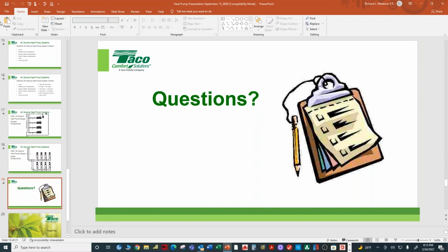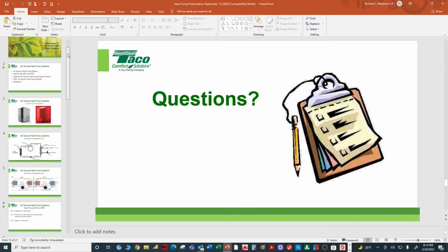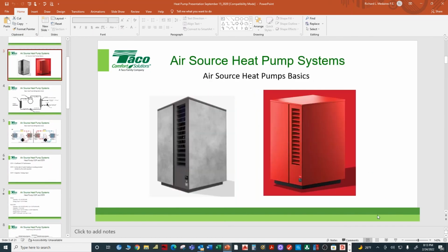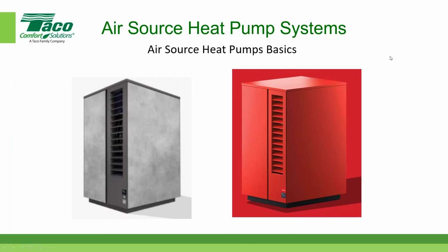I would like to address the question about the ones that are used as terminal units. Someone made the comment: we just changed the high rise from 545 heat pumps to chilled water fan coils. They're notorious for tripping out. I believe the terminal unit heat pump manufacturers have done a heck of a job making their products a lot better than that. That issue's not as prevalent these days, the noise and tripping out and all of that.